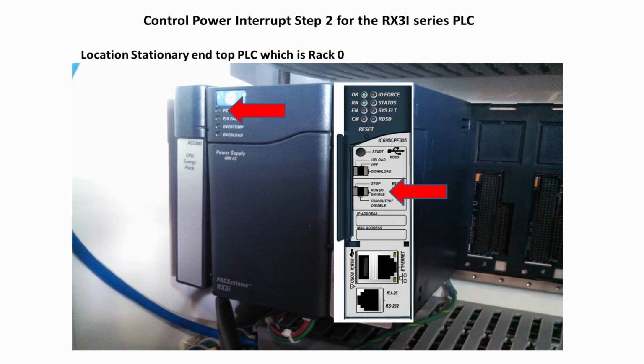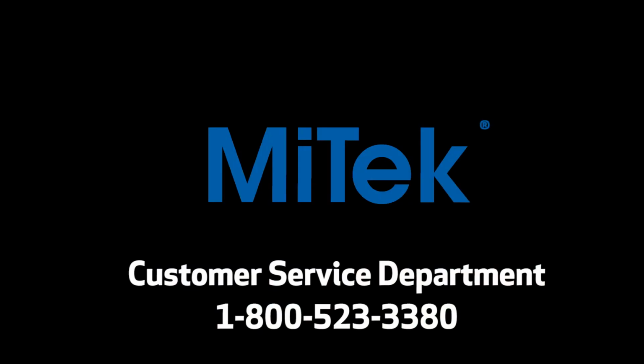Move the bottom switch on the CPU from the Stop Disable position to the Run Enable position and listen for the CR1 relay to engage and make sure it stays engaged. If the run light stays on, then reconnect the cable from the CPU energy pack to the bottom of the CPU. If the run light does not stay on, leave the cable off and repeat the process. If it fails after the second time, contact the MiTek Customer Service Department at 1-800-523-3380.